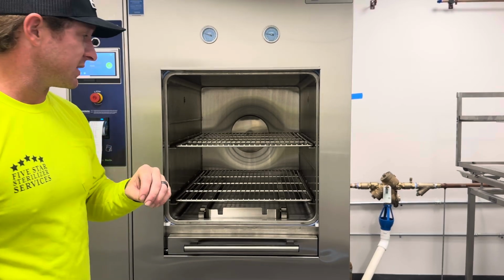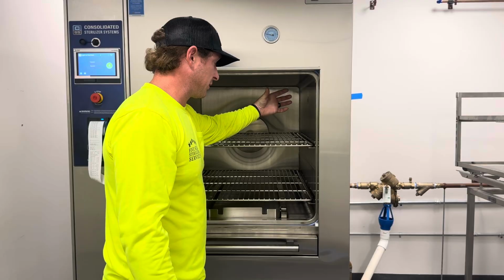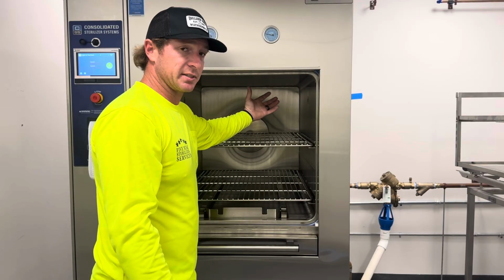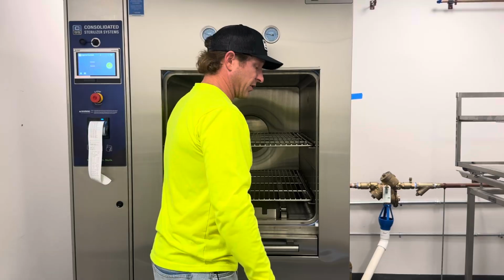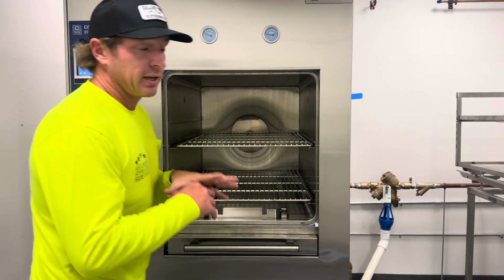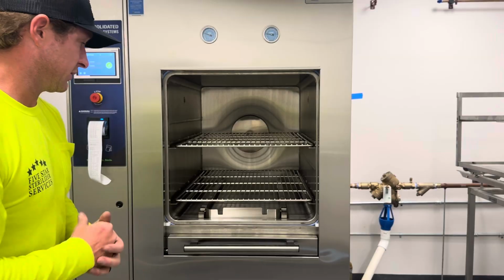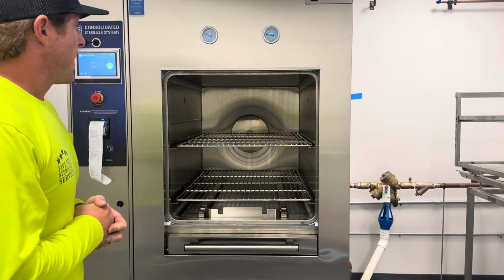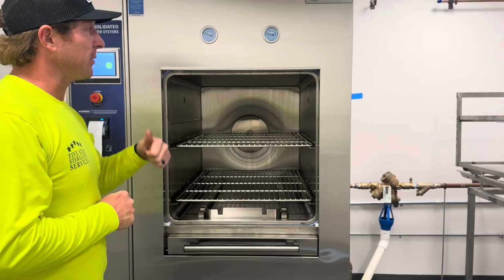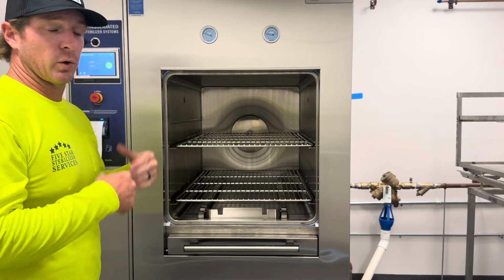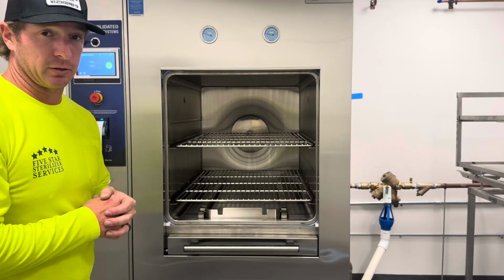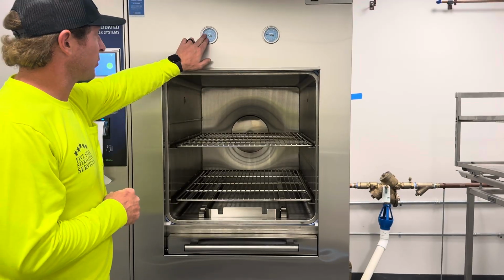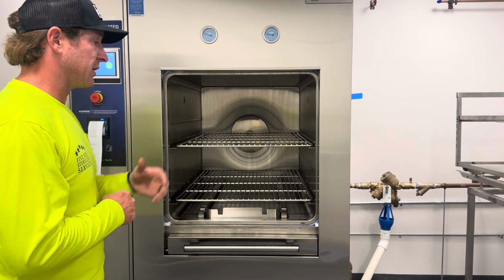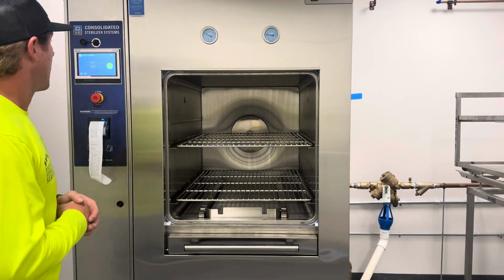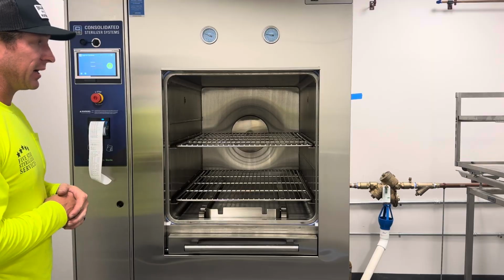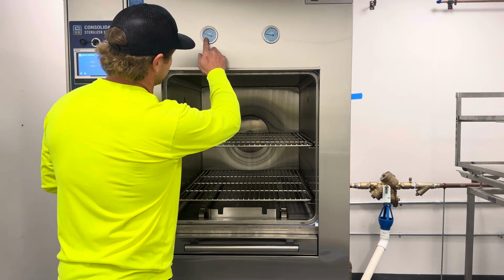ensures that we have a consistent temperature, whether you have a bottle or any contents of your load in this corner of the autoclave versus that back corner of the autoclave. You should have an even distribution of temperature. So the jacket helps us with that. This machine pulls steam from the jacket and the chamber when you start a cycle to start sterilizing your load. So it's very important that we have pressure inside our jacket as well as our generators before you start a cycle. One good way to tell if this machine is ready to run is look at the pressure gauge.